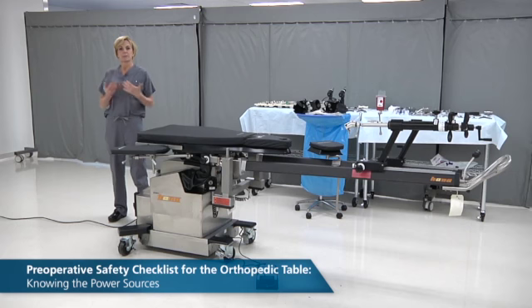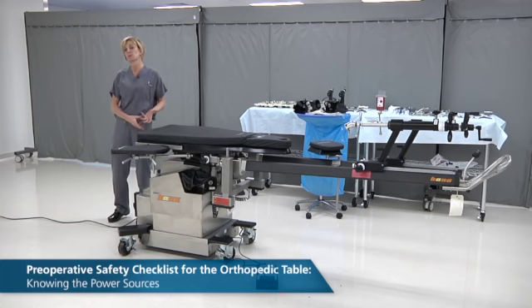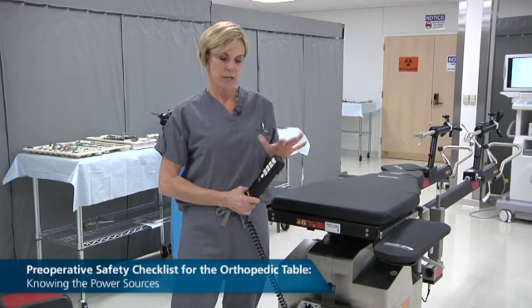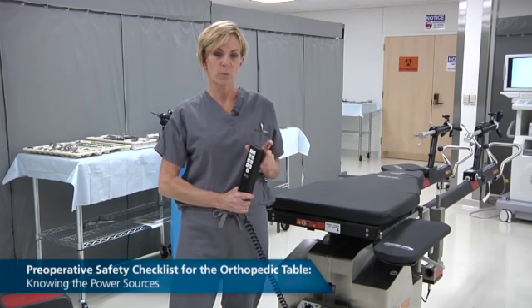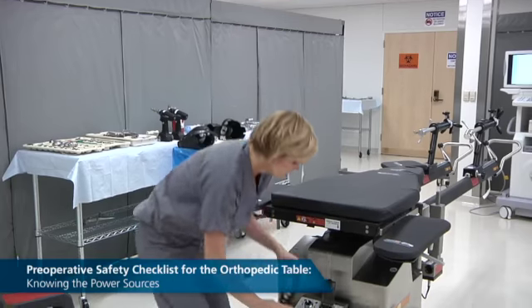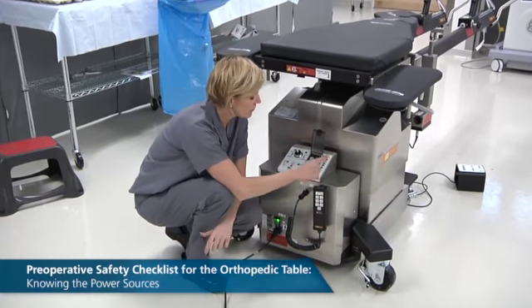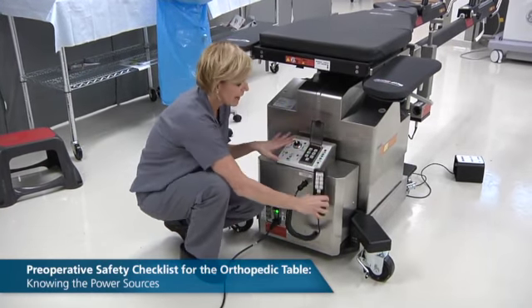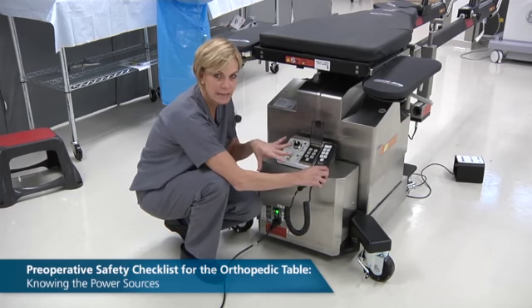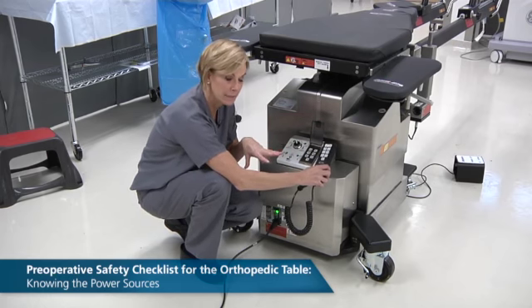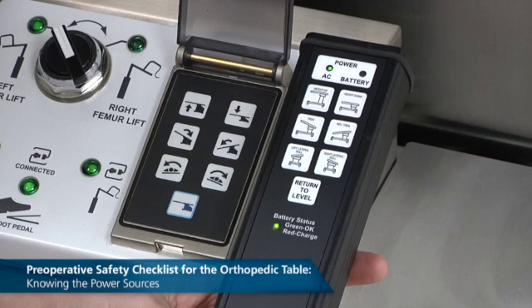Every once in a while, the table doesn't seem to be working. Of course, the first thing to do is check that it's plugged in. If it's not plugged in, there's a routine to go through to reset the table base. So the hand control is one way to work the table, but a second way is that on the base of the table itself, there's a keypad. Now the keypad and the hand control have the exact same 7 command buttons. The height up, the Trendelenburg, and the roll, as well as the return to level.